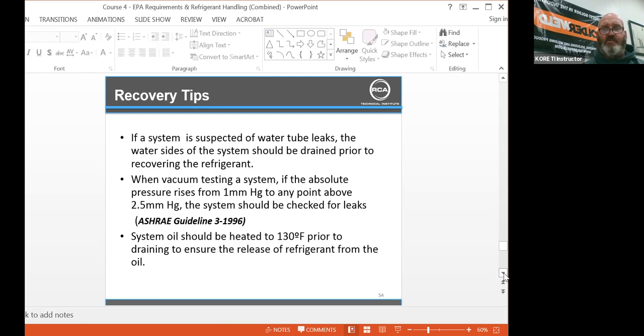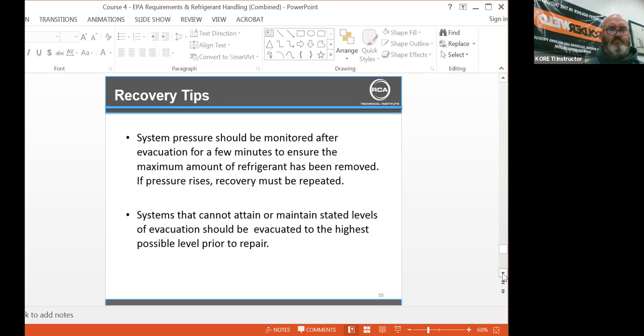And then the old term used to be called blank off. We would blank off a system in a deep vacuum and make sure that it does not rise above a certain point. Guys that are doing Walmarts, they know all about blank off because they have to do that before Walmart will approve a system start. System pressure should be monitored after evacuation for a few minutes to ensure the max amount of refrigerant has been removed. If pressure rises, recovery must be repeated. Systems that cannot attain or maintain a stated level of evacuation should be evacuated to the highest possible level prior to repair. So again, we're looking to see if any refrigerant rises after you pull it down. If it starts to float back up, you've got additional refrigerant that you need to pull out.